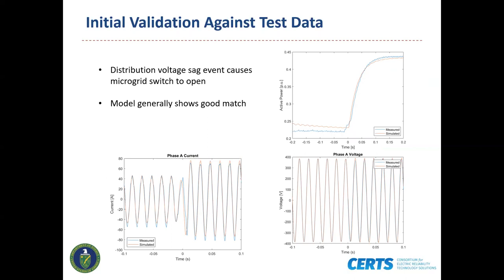There was a voltage sag on the distribution system, and the control logic of the microgrid switch caused it to open, which caused the microgrid to transition from being grid connected into island mode. Here we see that happened at t equal to 0 seconds. In the top right, you see the active power from one of the inverters. At t equals zero, you see a jump in the active power as it takes on the extra load from the microgrid. Then there's a snapshot of the waveforms on phase A for the current and voltage.